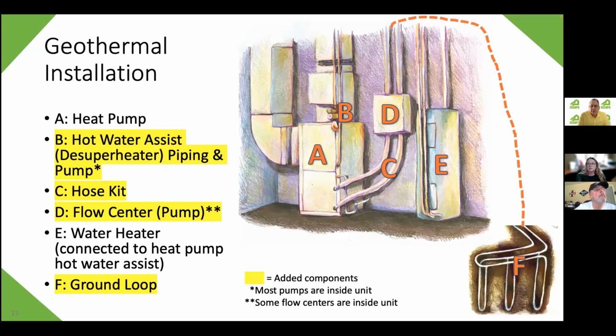When we look at geothermal, these components here, some of them would be additions, depending upon how the installation goes. If the contractor subs out the loop, the loop contractor may handle just the outside portion, or in some cases may handle piping all the way to the heat pump. If that loop contractor handles piping all the way to the heat pump, then really it's less components and less labor than either the gas furnace installation or the air source heat pump installation. You still have duct work, you still have to set the unit, but really it's simpler. And I don't think we think about that much. We're kind of used to talking about all the adders for geothermal, but in some cases we actually have less to have to deal with. So that's kind of important from that respect.